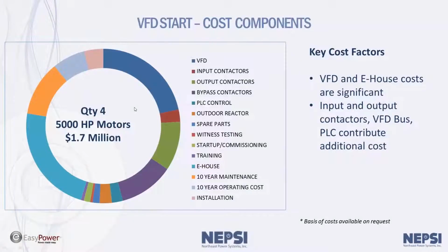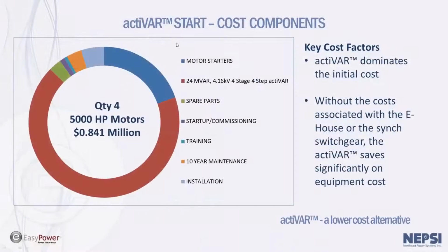So when looking at the cost of a 4-motor VFD start system, which includes the sync transfer bus, the bypass breakers and the e-house, a typical cost spread over a 10-year period, which includes the installation costs as well as the operating and maintenance costs, we come up with a cost of about $1.7 million. If I were to compare that to a capacitive start or an actiVAR system, the cost is on the order of $841,000. So there's significant cost savings when looking at a capacitive start actiVAR system in comparison to a VFD start system.